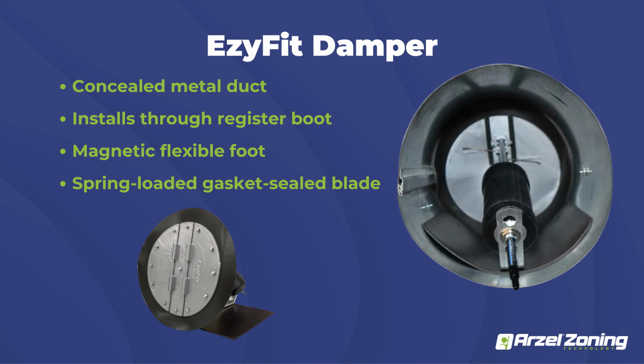One of the things I would recommend if you guys do any of these insertable dampers, make sure you guys leave yourself an access loop. So take a foot of tubing, roll it up and stick it behind your damper so that you're actually able to remove the dampers out of the ductwork without having to reach in and try to disconnect your tubing while it's in there. That's really the best thing I can say with these.